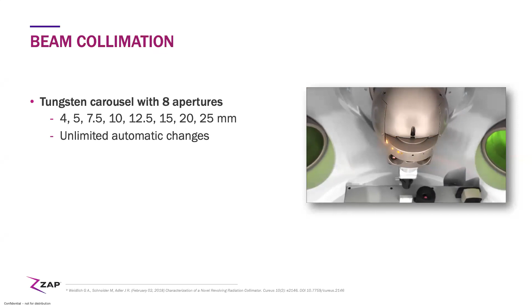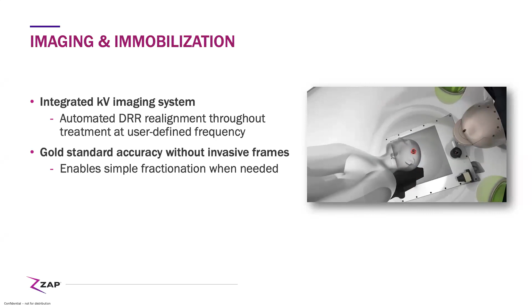The KV imaging is derivative in many ways of what we did with the CyberKnife. From multiple angles throughout the entire procedure, we acquire real-time images from the amorphous silicon panel that we have embedded inside the device, paired with the KV source. In real time, these images are correlated against DRRs developed from the patient's CT scan prior to treatment. Within seconds, we can deliver sub-millimeter targeting accuracy, and this gives you frame-like precision without the need for pins in the skull.